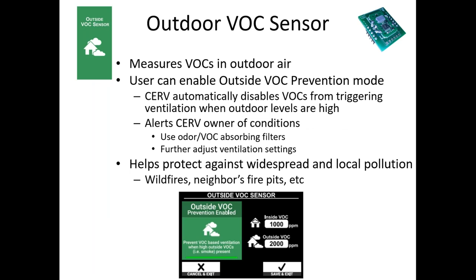The outdoor VOC sensor is an option that you can purchase. This goes in the outdoor airstream and lets us measure the VOC levels coming from the outside. It can either just be used for informational purposes to track what's going on outside, or the user can enable the outside VOC prevention, where the CERV will monitor what's going on outdoors versus indoors, and it can alter the operation and disable VOCs from triggering ventilation. So if you have wildfires or neighbors that like to burn things or other outdoor pollutants that may be of concern, bringing those indoors can increase the indoor VOC levels, but bringing in more fresh air because those levels have increased would just make things worse.